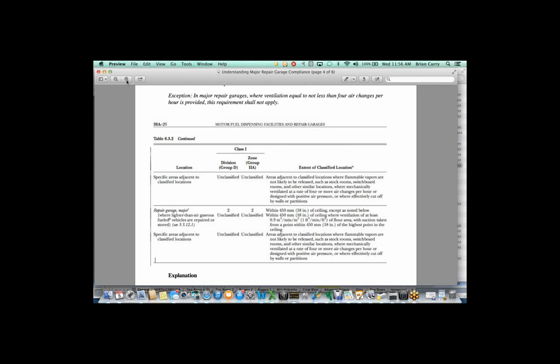So that system would be interlocked with the heaters, and we've done it a couple different ways. I've either used the methane monitoring control system to shut off the gas supply to individual heaters, or I've used it to shut off the main gas valve going into the building where I kill all the gas, which in turn would kill all the heaters at the same time immediately. It would open up an overhead door if it needed, or interlock my exhaust with a methane monitoring system to where the intake for the exhaust would open up with the exhaust fans.